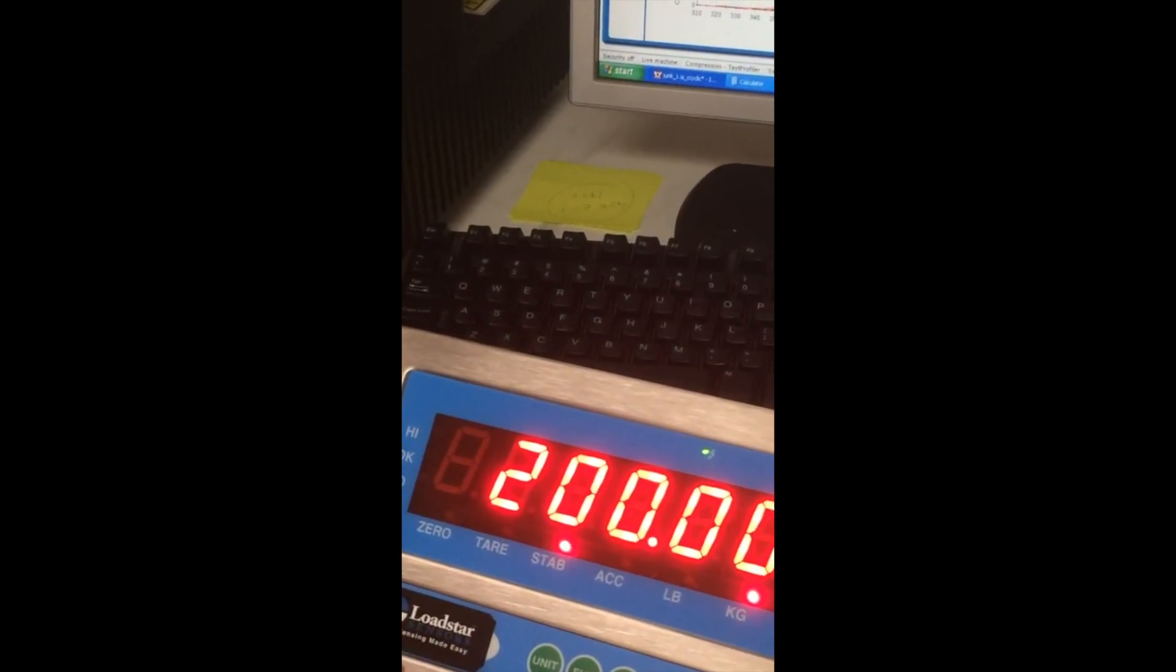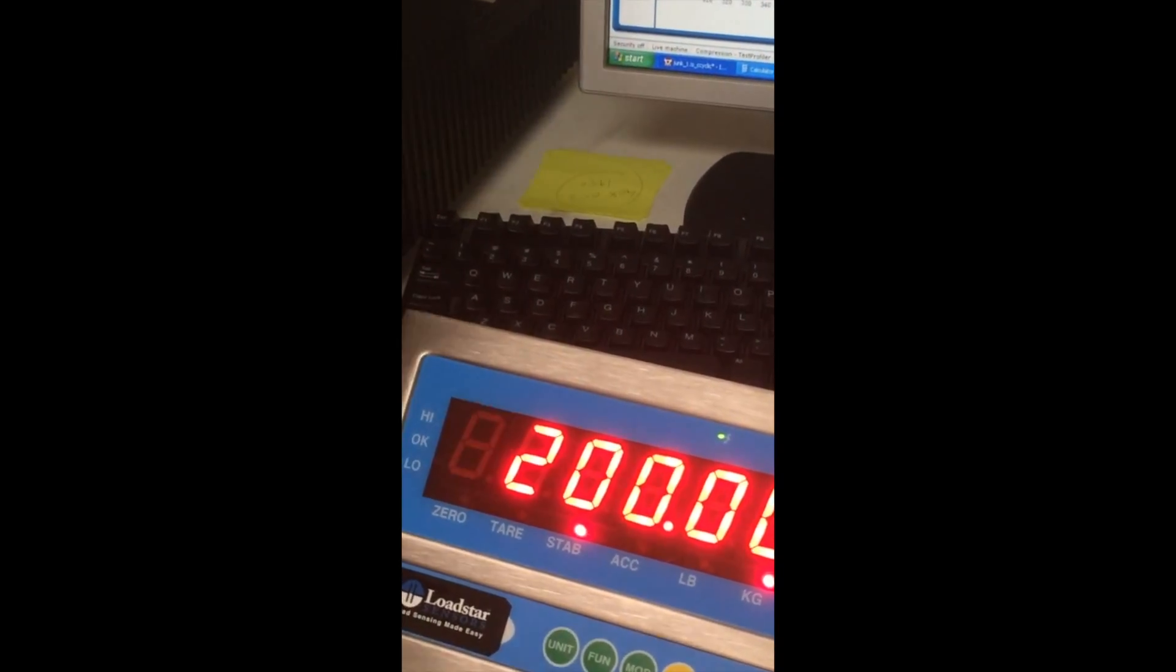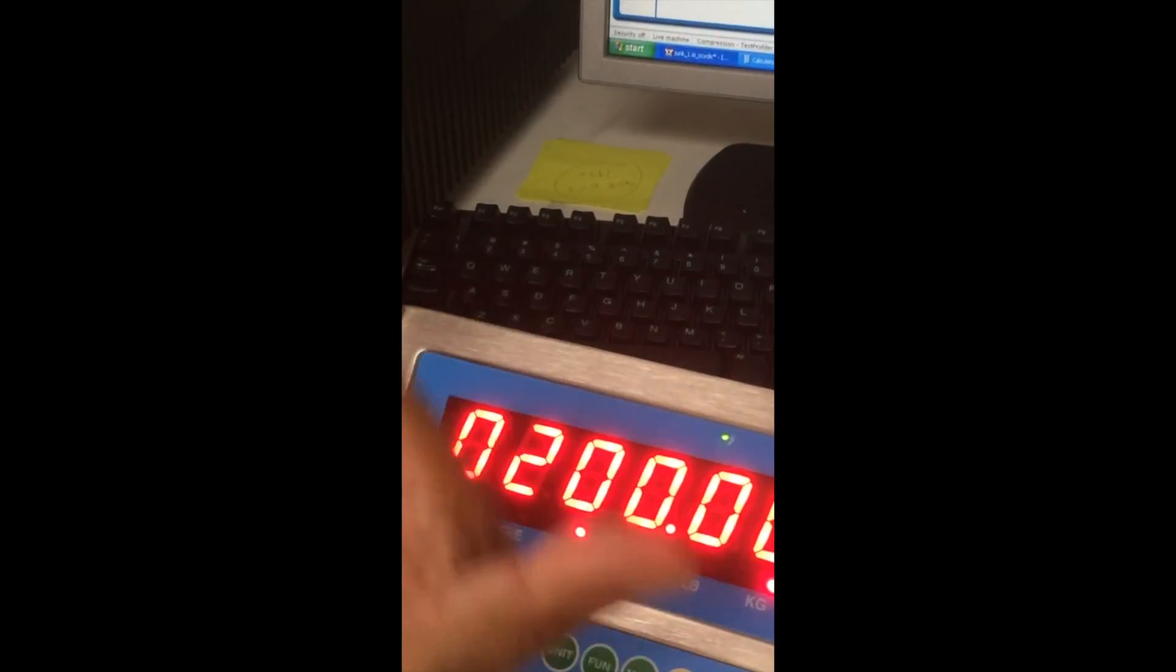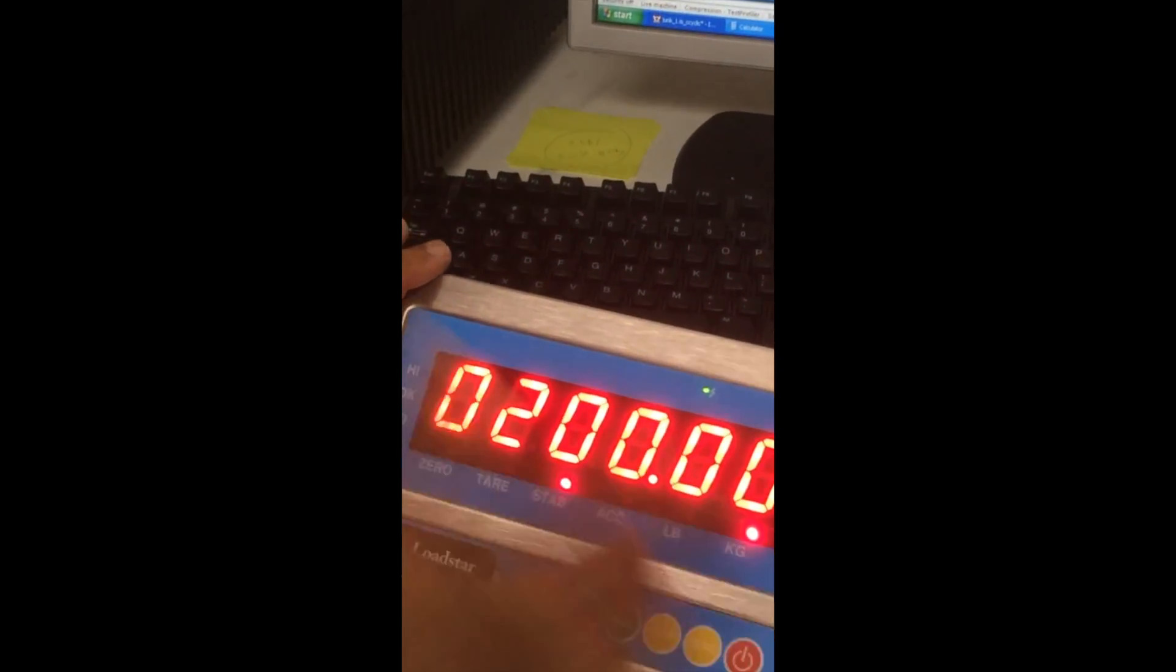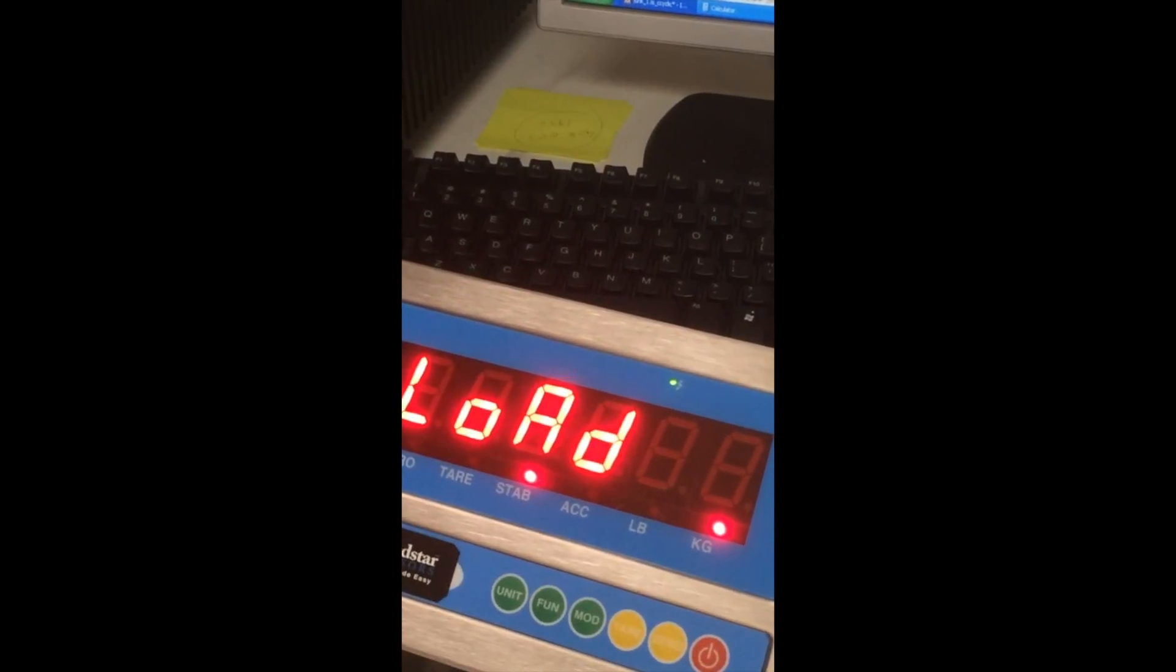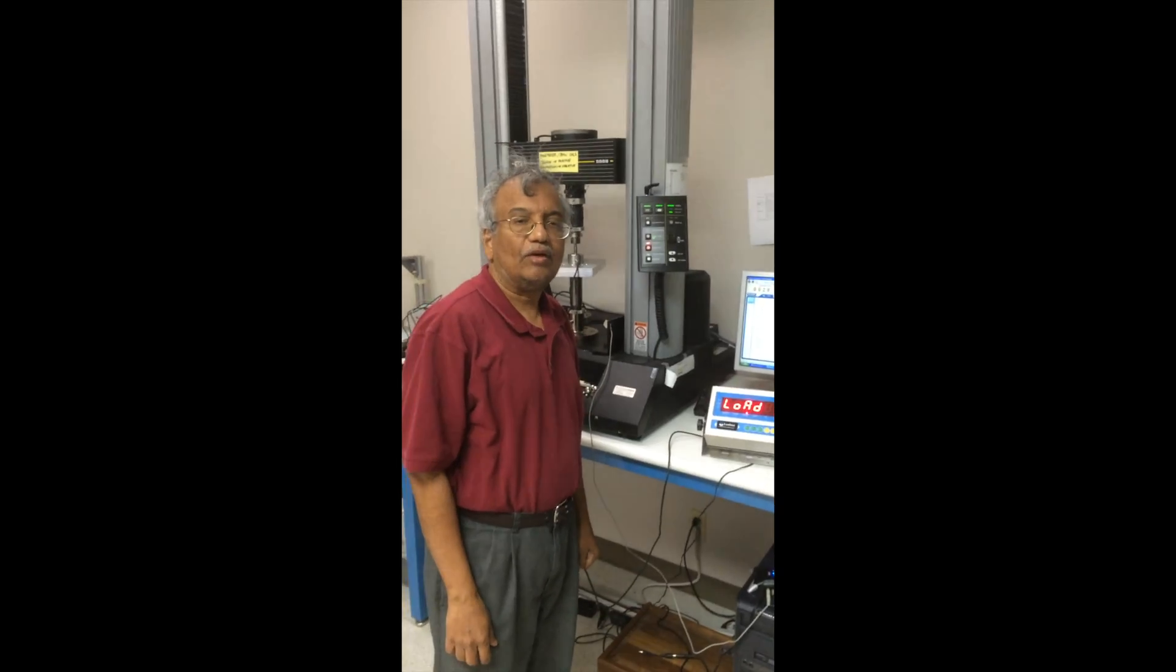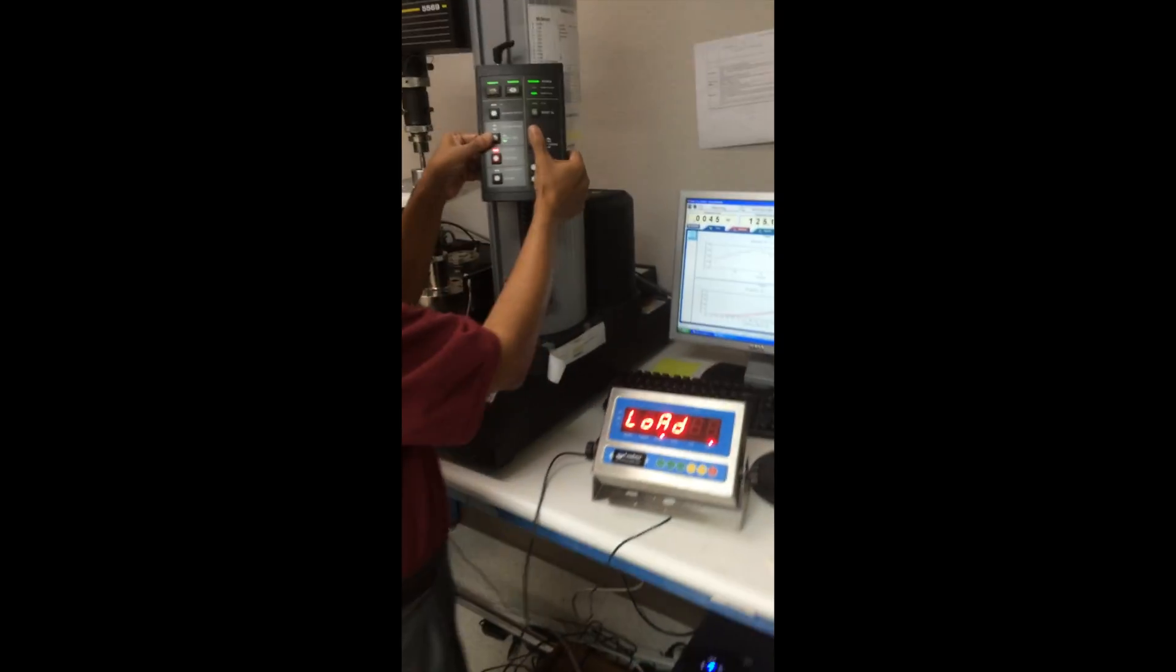Now it says what's the weight. If you don't have a 200 kilogram, let's say you only have a 100 kilogram load weight, you can change this to 100 and then press function. I am going to apply 200 kilogram, the full load. Press function. Now it says load. Now I am going to apply 200 kg to the load cell, the full load.